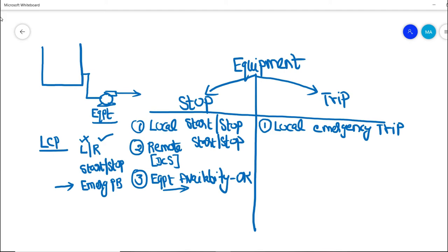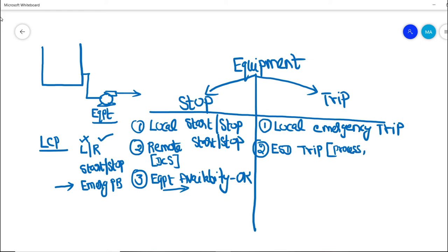Similarly, if the area operator is not available in the field and an emergency shutdown trip command is activated, the equipment will also get into trip. ESD trips may be caused by process upset or electrical faults — such as earth fault or overload — or by F&G alarms or trips, such as confirmed fire or confirmed gas release conditions. These scenarios will initiate an ESD trip and that ESD trip will trip this particular pump equipment.